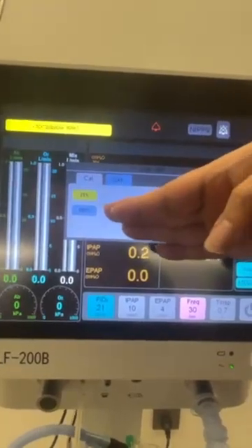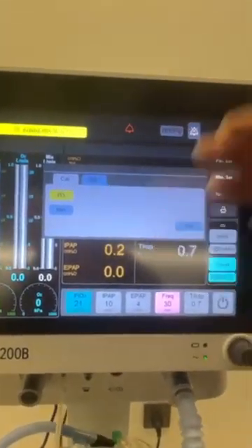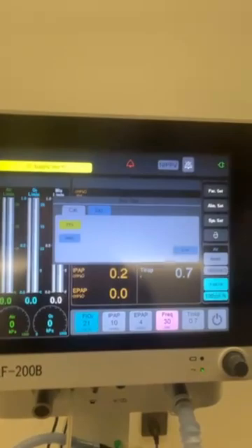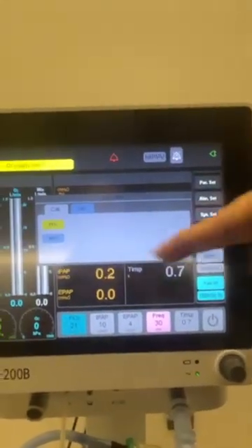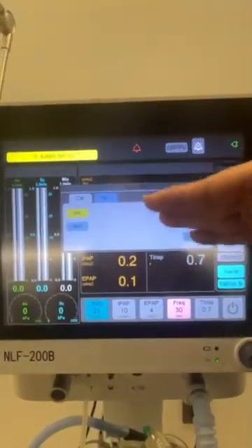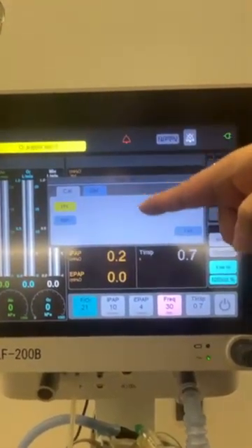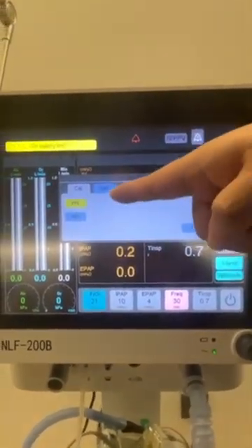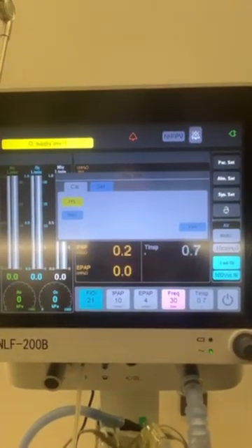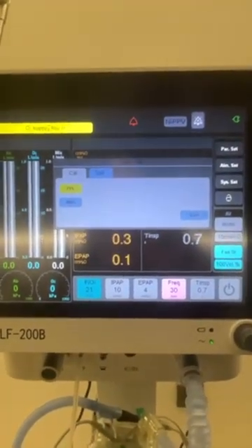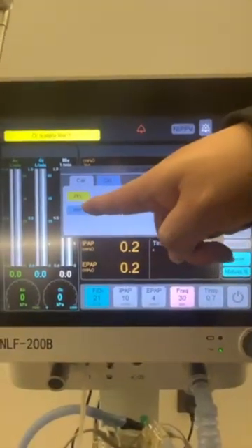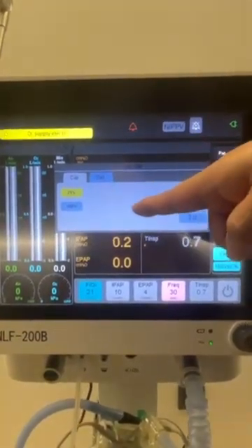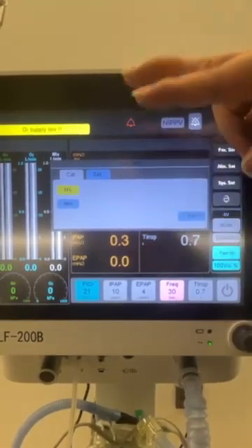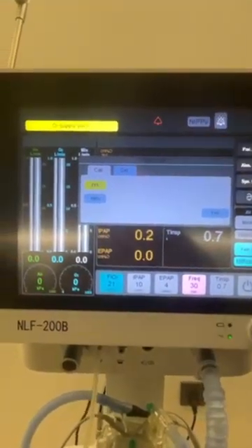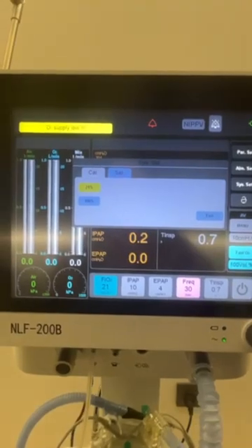So how to calibrate? We can see there are two points, 21% and 100%. For 21%, we only connect with the air compressor and not with any oxygen. We just press it, and after around 1 to 2 minutes, it will show complete. Then we change to 100%. Before we press 100%, you disconnect the air tube and only connect with pure oxygen. Then we can press the 100% button. It also needs about 1 to 2 minutes, and it will also show complete. When both are completed, the calibration is finished. Now you can use the machine very accurately.